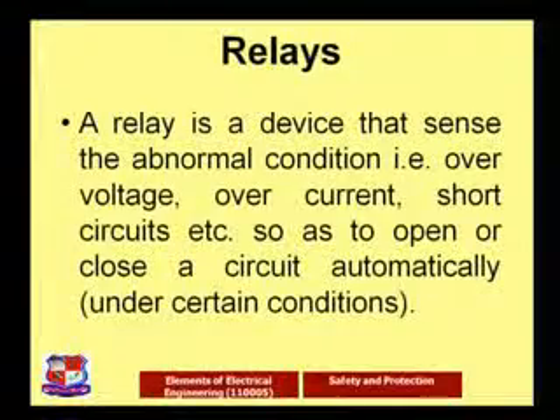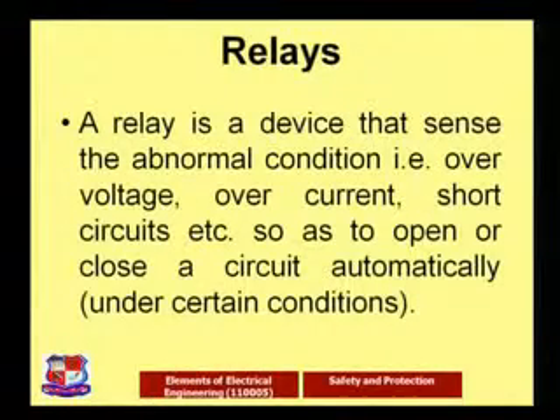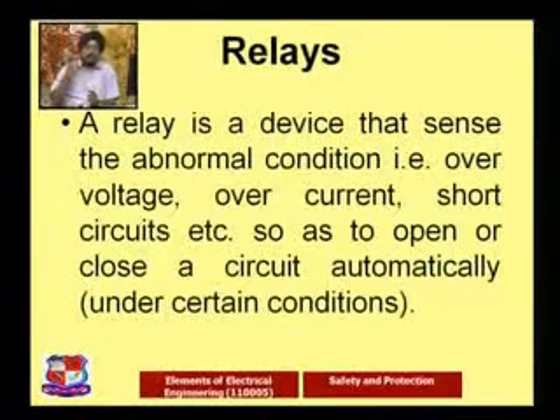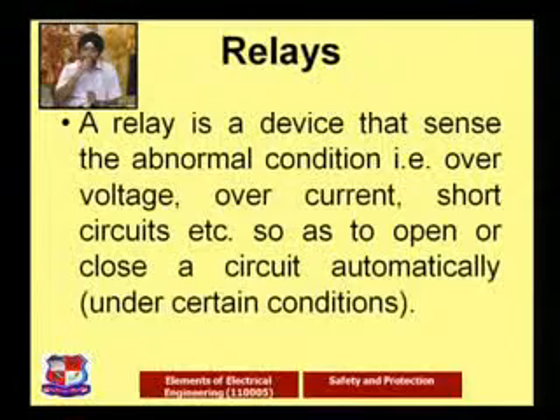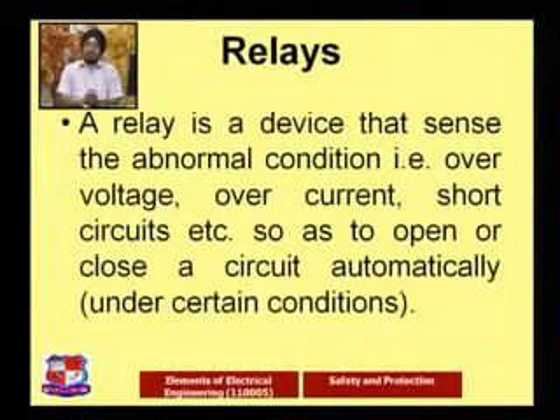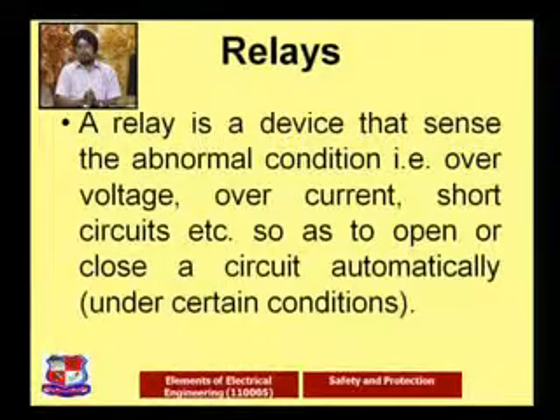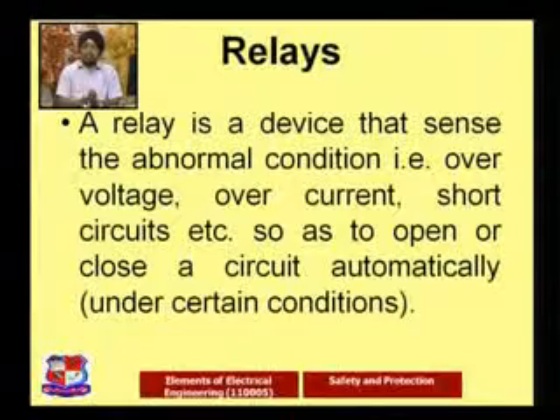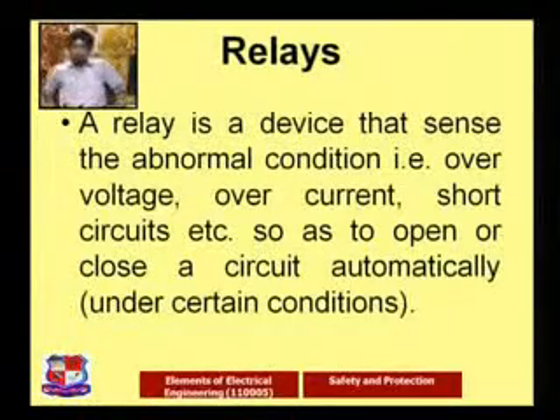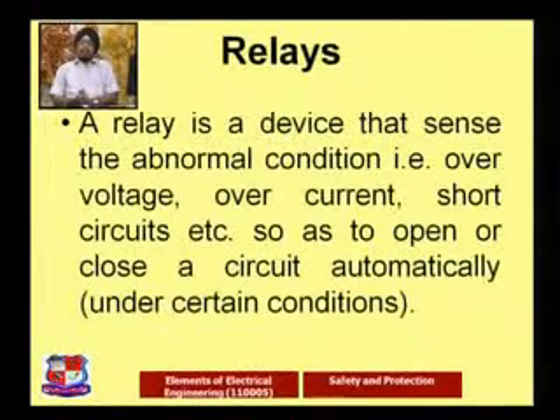Let's go with the relay. A relay is a device that senses the abnormal condition. Again I will define the abnormal conditions, and keep repeating them so we keep in mind which conditions are abnormal: over voltage, over current, and short circuit. So as to open or close a circuit automatically under certain conditions. This is very important because it can open as well as close.